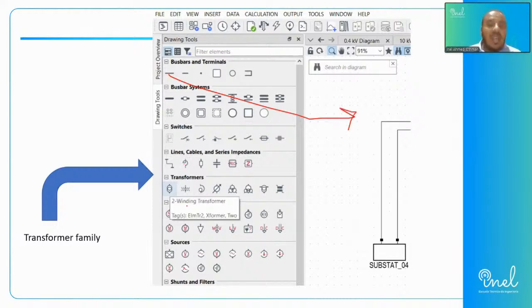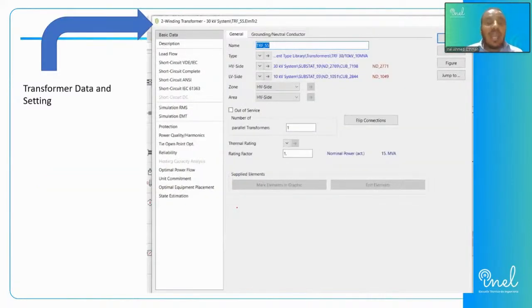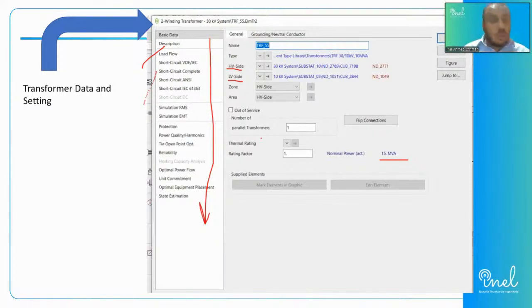So, for example, if you need to add a transformer, you will find a family of components called transformer, where you can add such a transformer. After you drag and drop the transformer, by double-clicking on the symbol you are able to confirm all settings for it. You can confirm the low voltage side and high voltage side. You can confirm the megavolt ampere. You can do some settings for load flow, short circuit, and so on. So you are able to drag and drop to add a transformer, and from there you can adjust and modify the settings on your transformer.